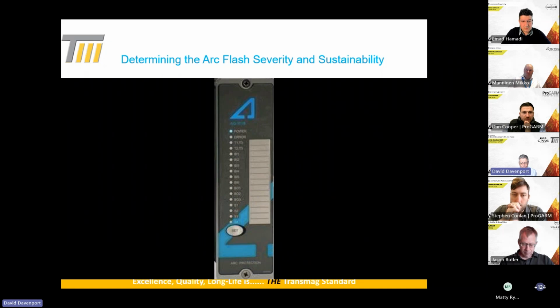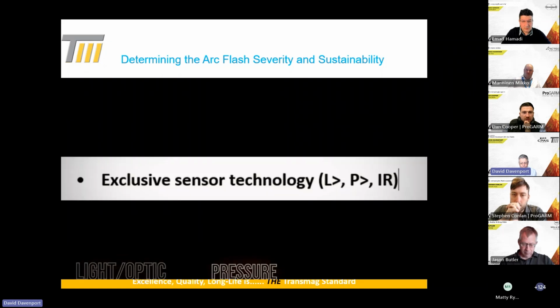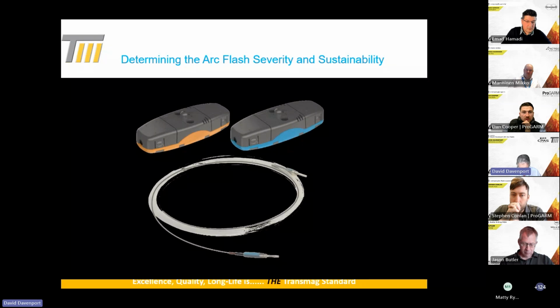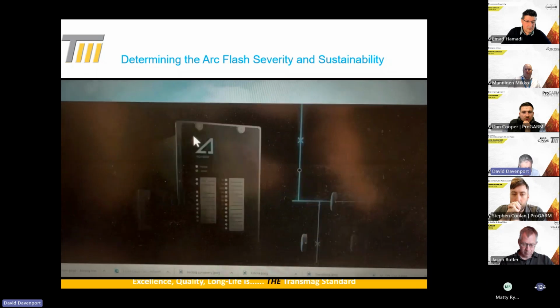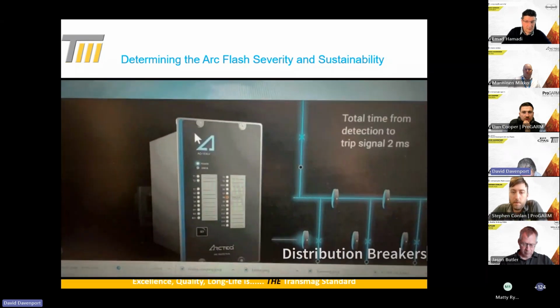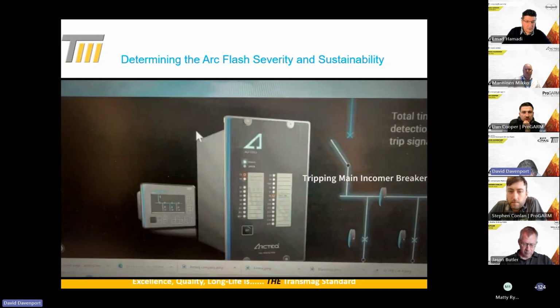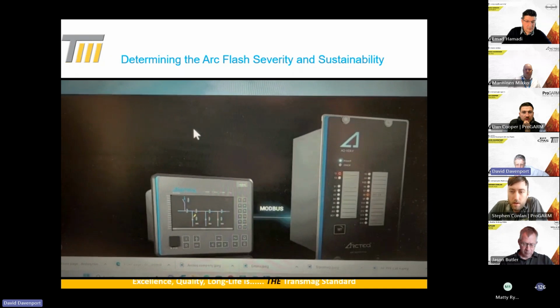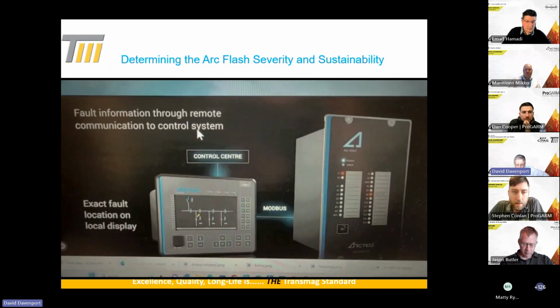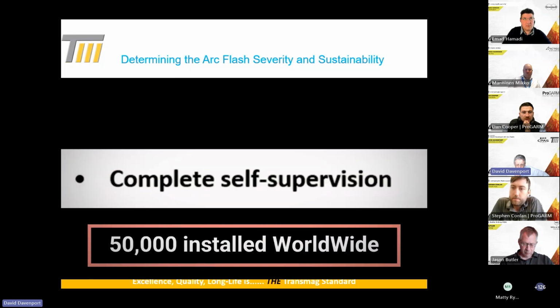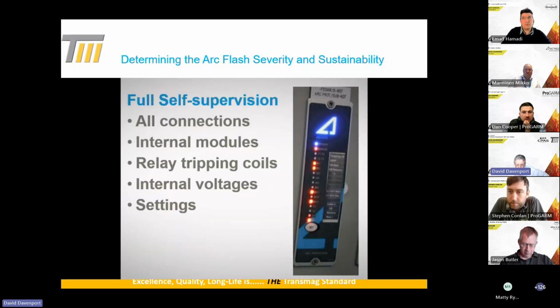The Arcteq relay can be operated by any selected combination of light, pressure, or inrush overcurrent. We connect to that Arcteq relay either sensors or fiber optics, or even both, at the most appropriate points, along bare bus bars, close to any terminations and, of course, any circuit breaker vicinity. These actuate at the outset or inception of an arc flash incident. Within 2 milliseconds the trip signal is triggered to open the incoming breaker that feeds that circuit and therefore isolates the fault. Arcteq relays, with over 50,000 arc flash relays in service globally and without a reported failure to affect an arc flash incident as described earlier.